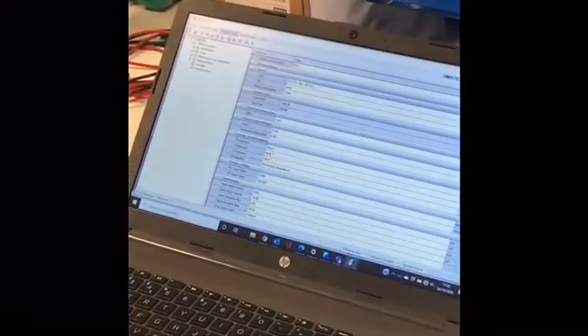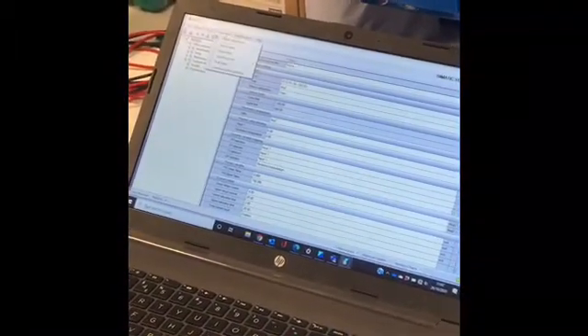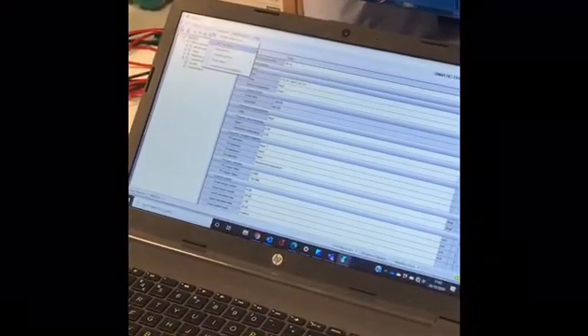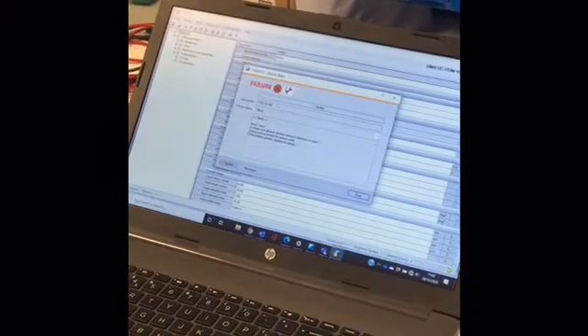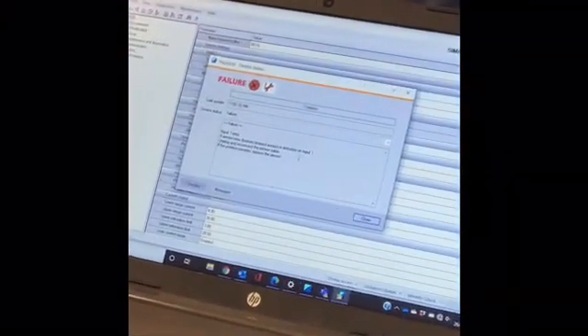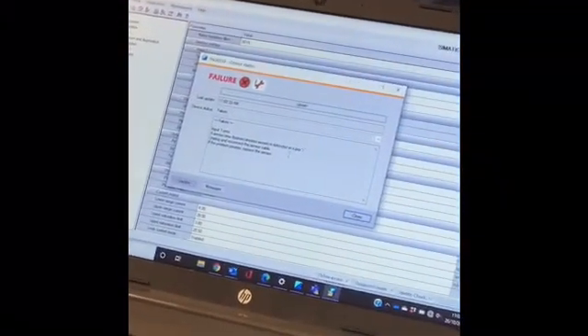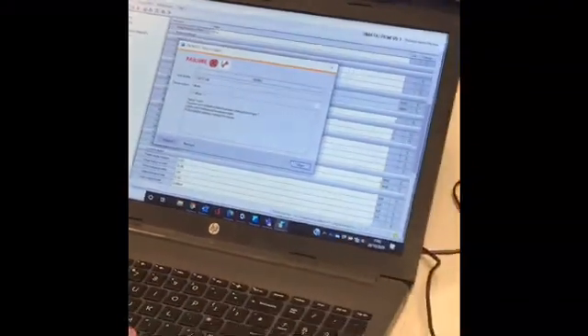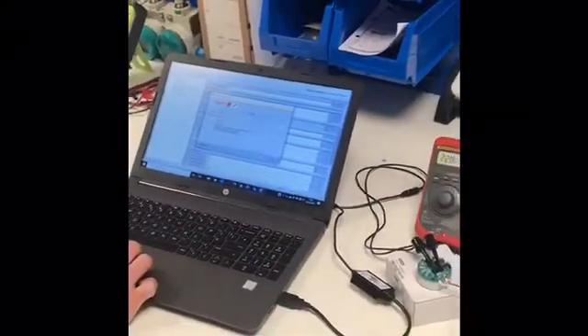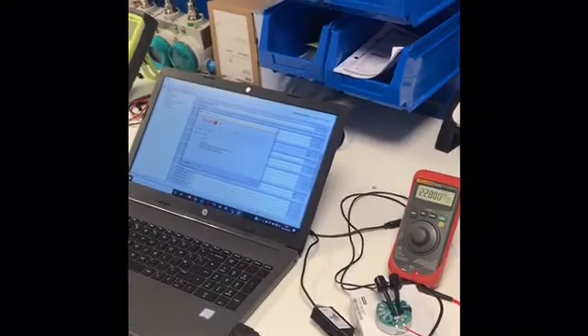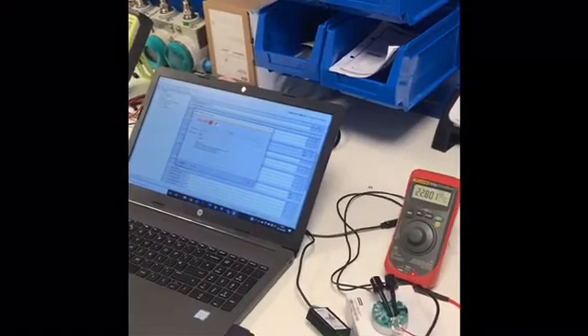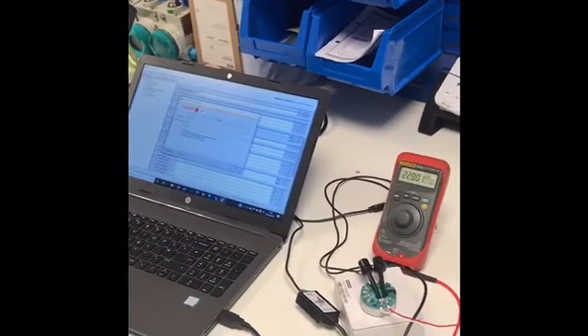And the reason for that, if we go to the device status, we can see that that's because there isn't a sensor connected to the transmitter. However, the configuration has been loaded correctly, so as soon as we do connect a sensor, we'll have a functioning temperature measuring device.